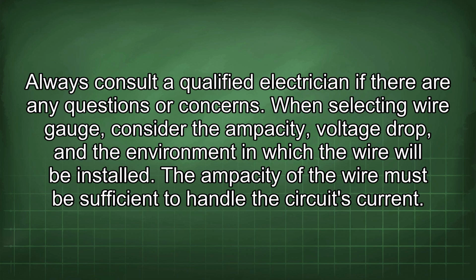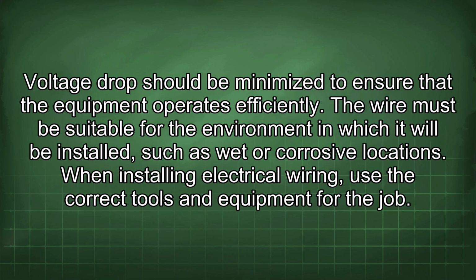When selecting wire gauge, consider the ampacity, voltage drop, and the environment in which the wire will be installed. The ampacity of the wire must be sufficient to handle the circuit's current. Voltage drop should be minimized to ensure that the equipment operates efficiently. The wire must be suitable for the environment in which it will be installed, such as wet or corrosive locations.